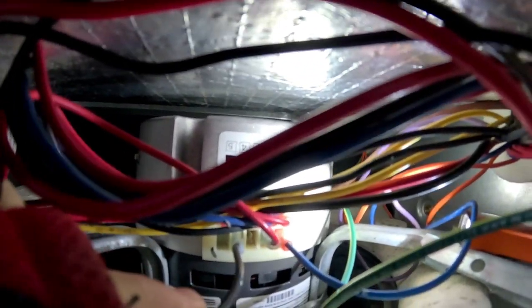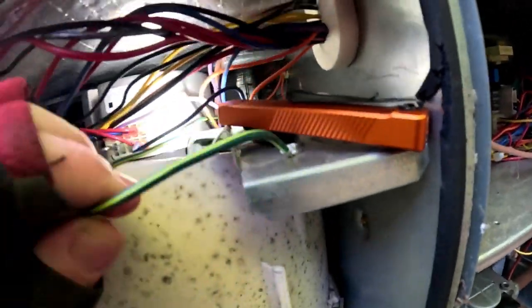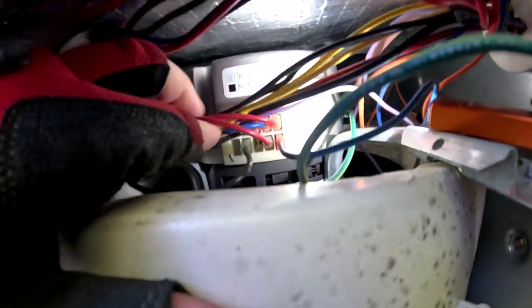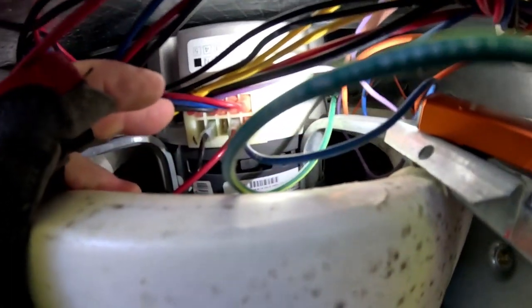Yeah, so these wires across the top are going to be our low voltage, and the wires on the bottom are going to be our high voltage, and that black wire that got chopped is going to be one of our hot wires. The ground is here, so this one's going to be our common for our low voltage. This red one is going to be, because it's a package unit, gas pack, it has 240. A furnace is going to have 115, so that's basically going to be your L1 and your L2. One would be neutral and hot if it was a furnace. This is a package unit, so it's fed by 240 volts. That's a 240 volt X13 blower in it.